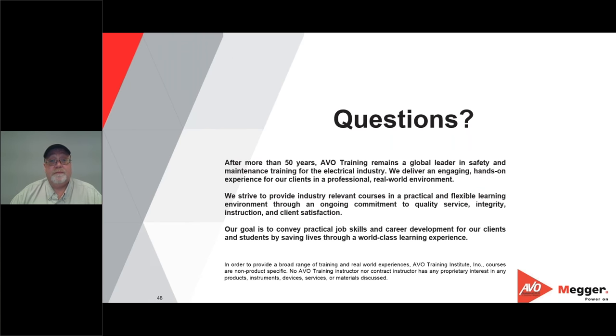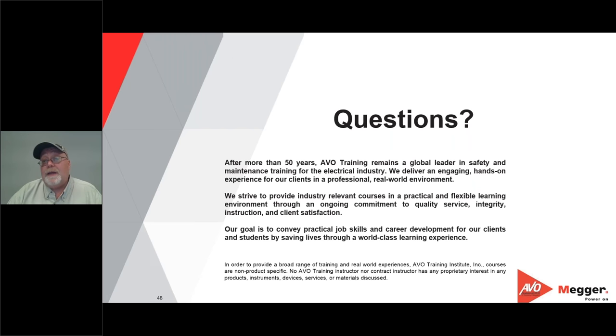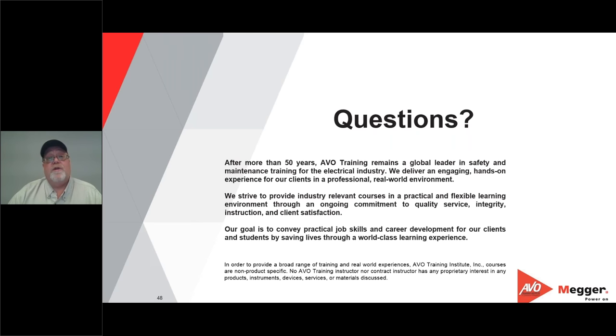Ray wants to know how isolation transformers affect harmonics. When dealing with voltage harmonics, they will propagate through a transformer. However, current harmonics typically will not. One of the most common transformers used is a delta-to-Y transformer. Triplen or zero-sequence harmonics won't propagate through a delta-to-Y transformer — they get trapped in the delta side since there's no ground path for them to get through. That's one of the key reasons delta-to-Y transformers are used: for harmonic mitigation.